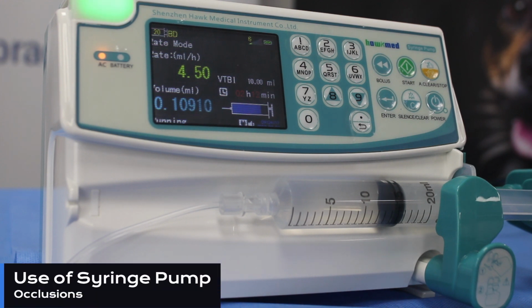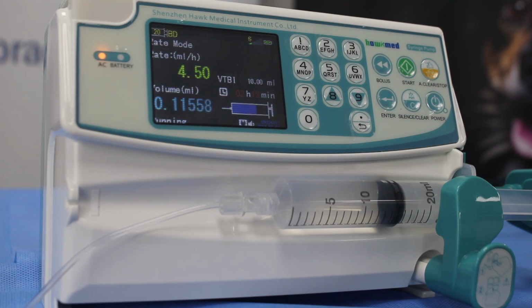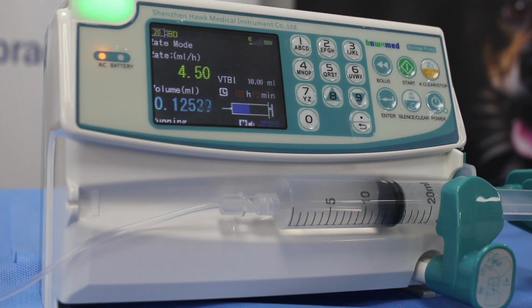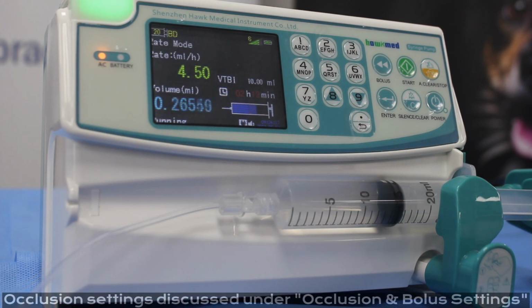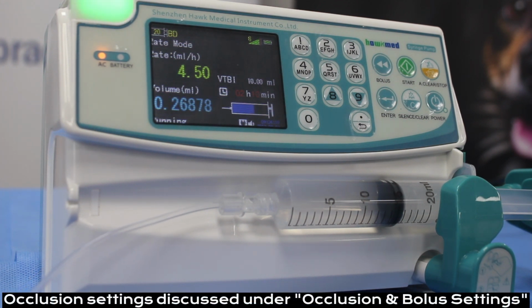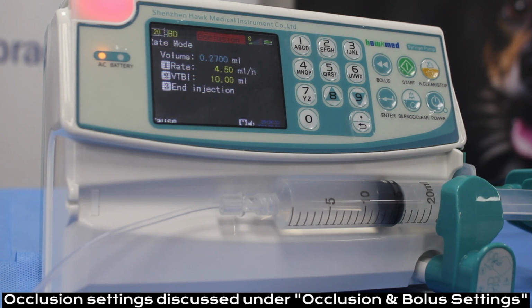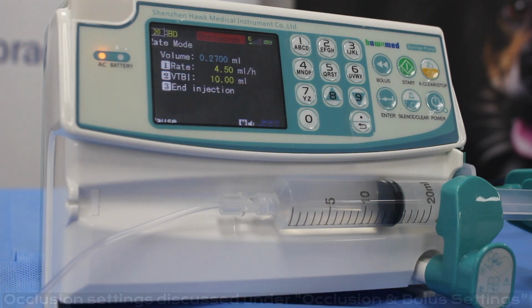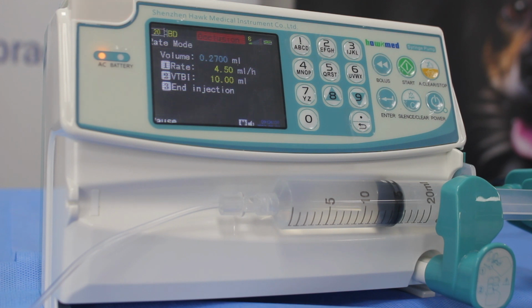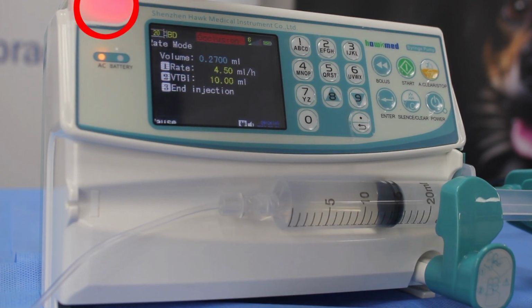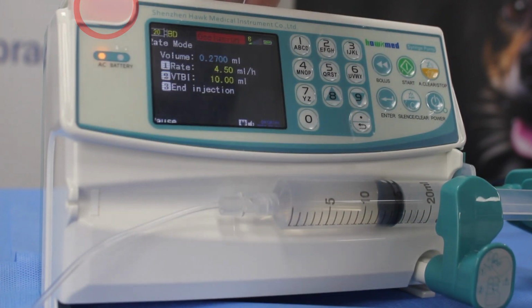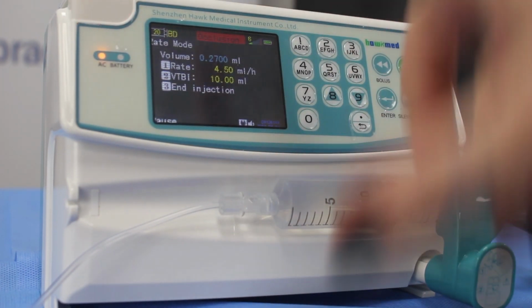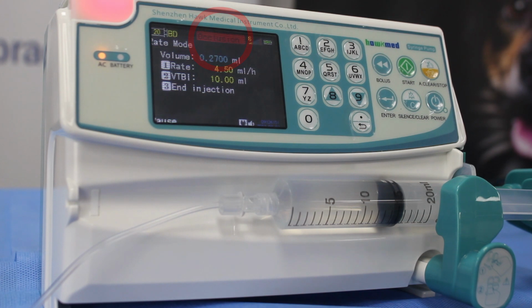If an occlusion is encountered, your syringe pump will stop infusing into the patient so that you can have the opportunity to resolve the issue. We'll clamp our line now to mimic this occlusion for you. Our pump has detected the occlusion. An LED light has started flashing to alert us to this. The infusion has automatically stopped and it's displaying occlusion at the top of our screen here.